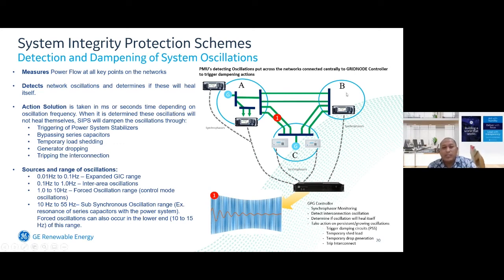So in this dampening system oscillation solution, there are PMUs detecting oscillation put across the network and then connected centrally to the grid node controller to trigger dampening action.